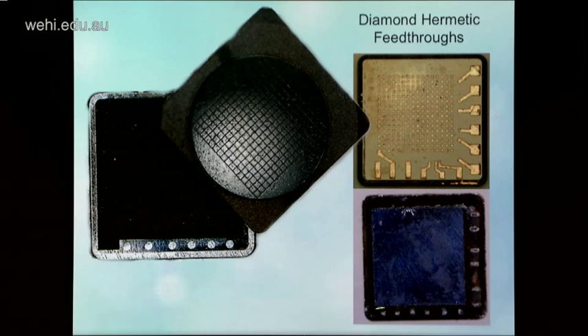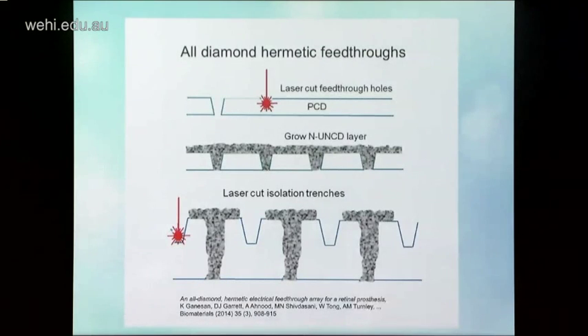Because if you are putting your ASIC on your electrode array, the electrode array has to be hermetic, it can't leak. So everything here has to be encapsulated hermetically so that it's protected from the body and the body is protected from it, as I'm sure you understand. So we needed a way to make this electrode array functional and hermetic in order to accommodate this. When you're getting to high electrode counts, you just can't have any leakage at all. So these have to be extremely, extremely reliable feed-throughs.